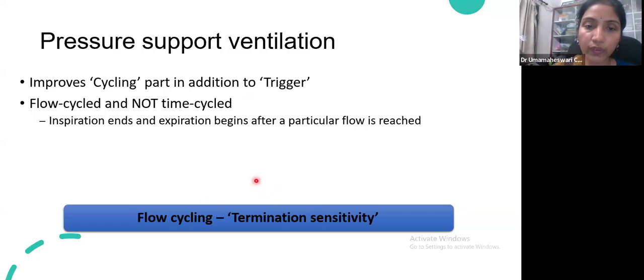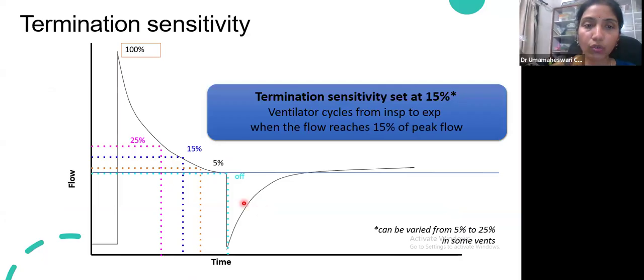So in flow cycling, you set what is known as termination sensitivity. So this is the flow graph. As the flow keeps on reducing, before the flow touches 0, that means the baby has stopped inspiration and is moving on to expiration. You can move the baby from inspiration to expiration when you are in PSV. Say, for example, you have set a termination sensitivity at 15%. The ventilator cycles from inspiration to expiration when the flow reaches 15% of the peak. So this is the peak flow, which is 100%. This is the flow at 15%. So you can decide on the termination sensitivity. You can keep 5% or 25%. Generally, the termination sensitivity is set at 15%.